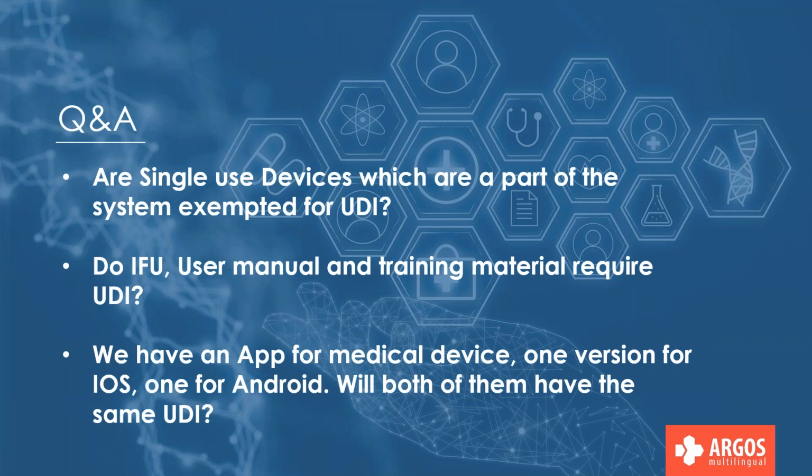Do IFU, user manual and training materials require UDI? No, that's not a requirement. However, think about best practices and whether it makes sense for you. I think it's a great way to connect all of your products and data and information together.